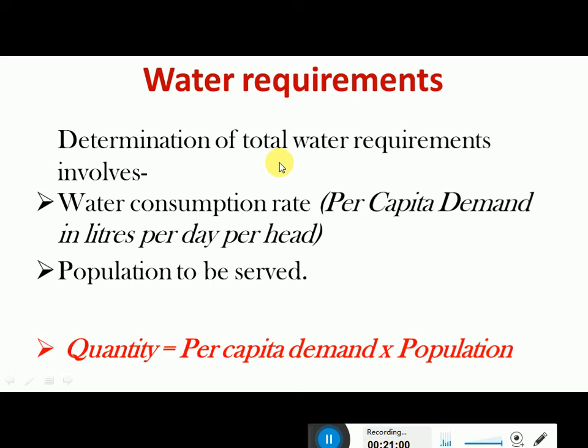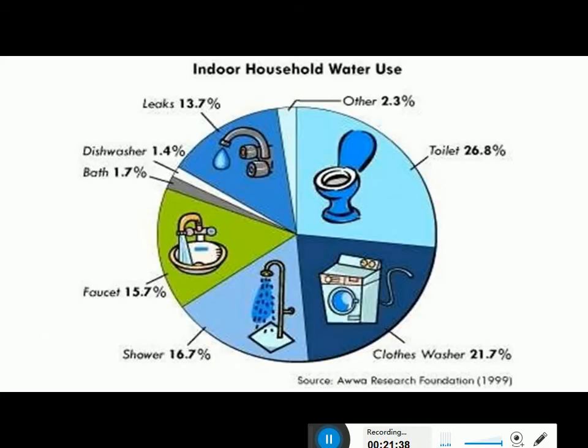Water requirement is the total water demand, given by per capita demand multiplied by population. We have various types of demand: domestic, industrial, fire demand, etc., which must be estimated based on the standard of living. For most Indian conditions, the per capita demand is around 150 LPCD. The water supply scheme is usually designed for 30 to 40 years of future population.